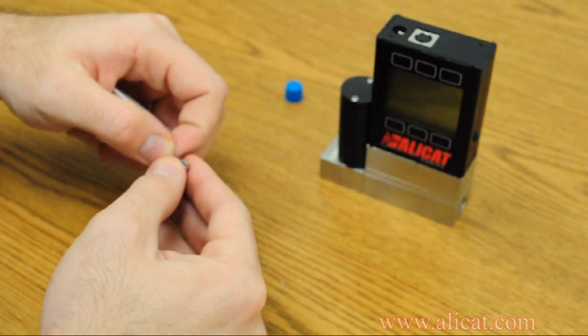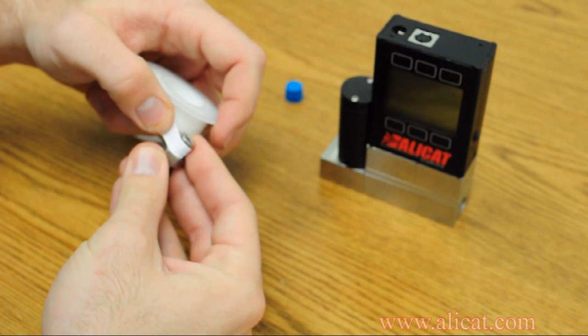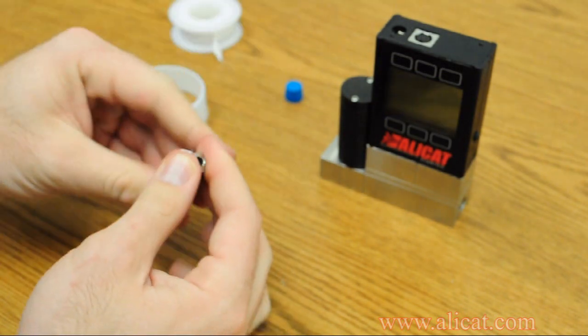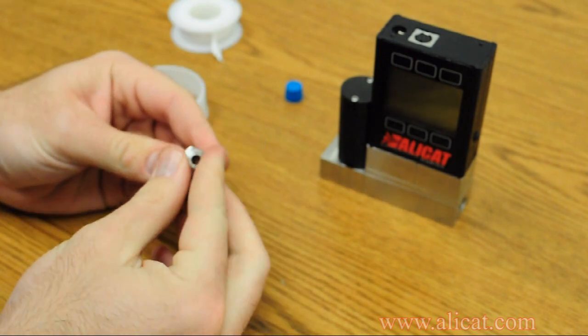For each fitting, wrap the Teflon tape around the threads in a clockwise fashion as seen looking towards the threaded end. Two to three complete wraps should be sufficient for most fittings. It is very important to leave the first few threads uncovered so that no tape can be sheared off and end up inside the flow meter.